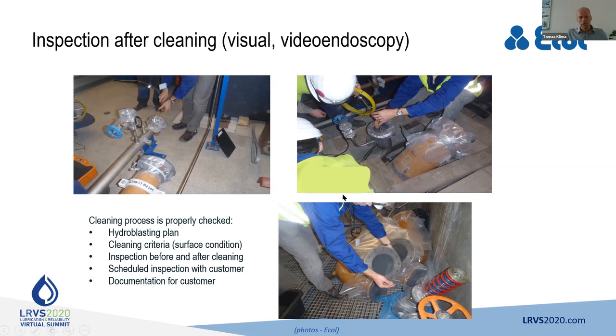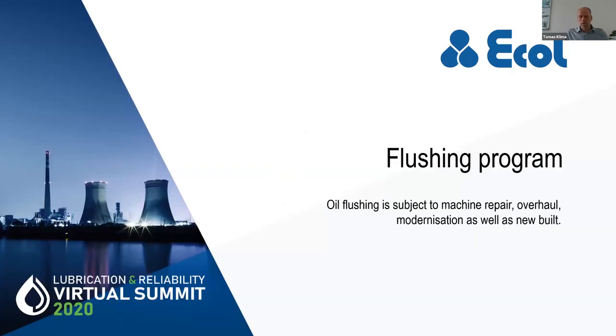The cleaning is done according to the hydroblasting plan. The cleaning criteria are set with the customer, and all the pipes are inspected before and after cleaning, which is of course documented for the customer. After the system is clean, there are certain flushing scenarios. Oil flushing is subject to machine repair, machine overhaul, of course modernization, as well as if the machine is newly assembled. All the time the flushing is part of the maintenance process.